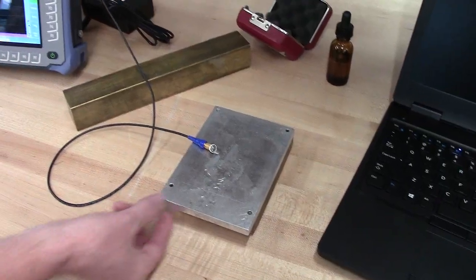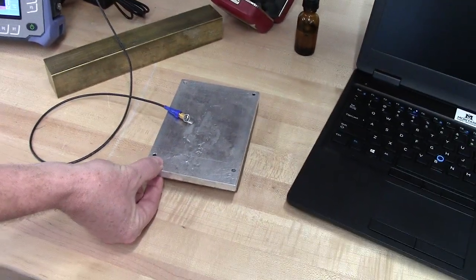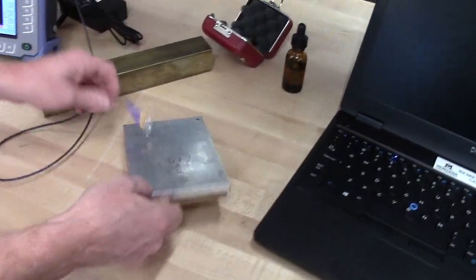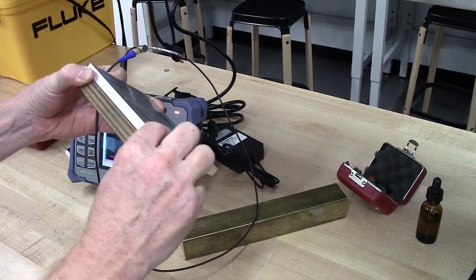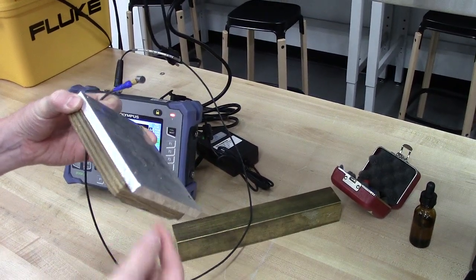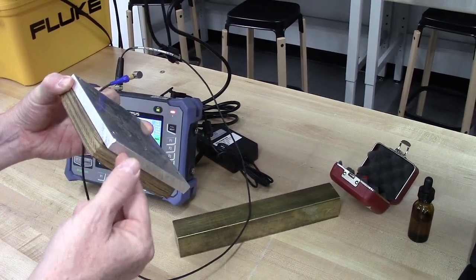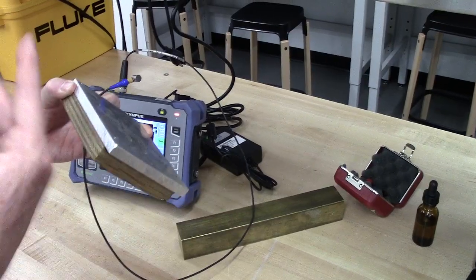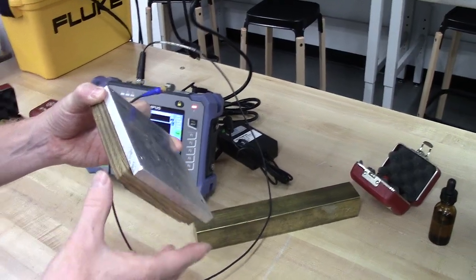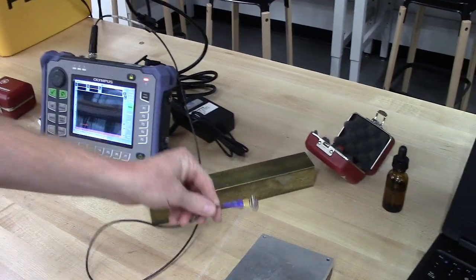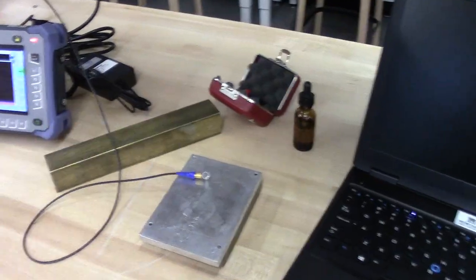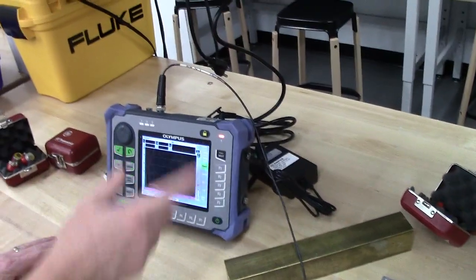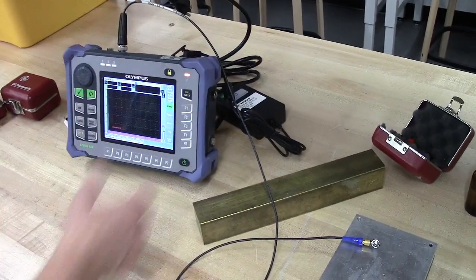So we have this known thickness out here where we don't have the aluminum block covering it. We can measure this thickness. And if we measure the time it takes to go through it and back, we can get the velocity. So that's what we want to do in this first step. So instead of inches, we want units of time.